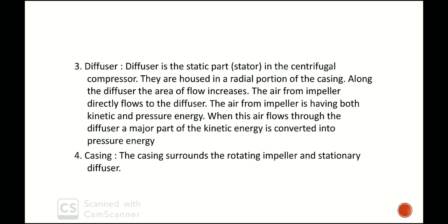Along the diffuser, the area of flow increases. As the area increases, velocity decreases as per the continuity equation, and pressure automatically increases. The air from the impeller flows directly to the diffuser, carrying both kinetic energy and pressure energy. As it flows through the diffuser, most of the kinetic energy is converted into pressure energy.